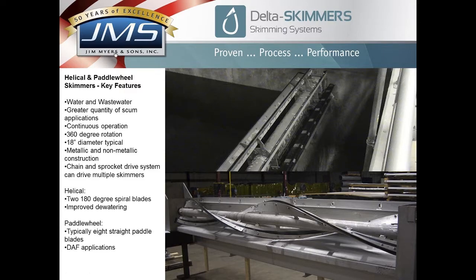But these paddle wheel and helical skimmers are different from scum pipes, and they're typically continuous operation, and they typically are for applications that have a greater quantity of scum, or the rate of development of scum is great enough that helps warrant continuous operation in these systems. They're typically 16, 18-inch diameter, typically stainless steel, although we can provide fiberglass as well.